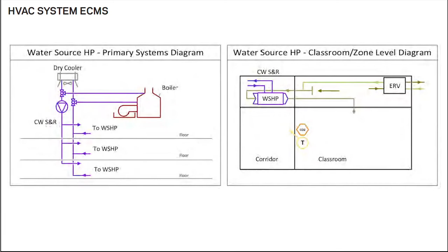The condenser water loop connects in the classrooms to individual water source heat pumps for each classroom. So there's something nice about having a water source heat pump individual to every classroom. You have a little bit better controllability of your heating and cooling per classroom. And in this scenario, we also investigated individual ventilation, not a central ventilation system like the previous scenario with the rooftop RTUs, but individual ERVs in each classroom.